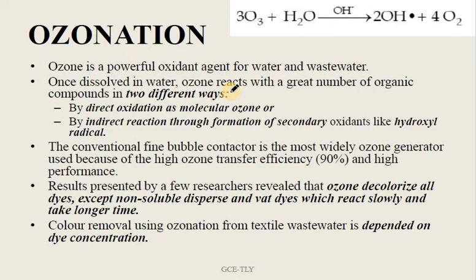In the ozonation process, we all know ozone is a powerful oxidizing agent for both water and wastewater treatment. Once dissolved in water, ozone reacts with a great number of organic compounds in two ways. One is by direct oxidation as molecular ozone, or by indirect reaction through formation of secondary oxidants like hydroxyl radical. The hydroxyl radical is formed from the reaction 3O3 plus H2O along with OH- ion in an alkaline environment, which gives 2 OH radicals.